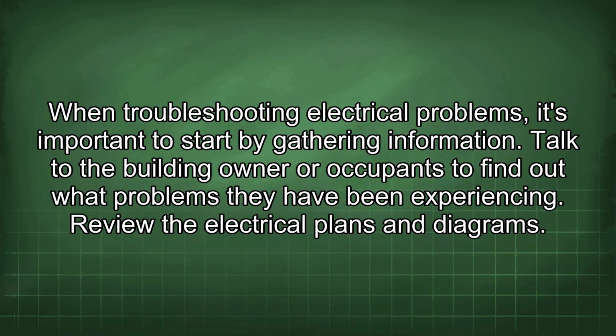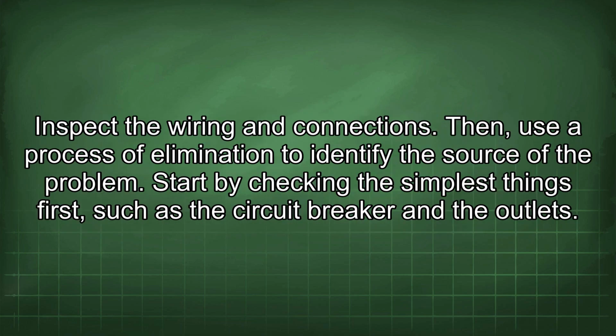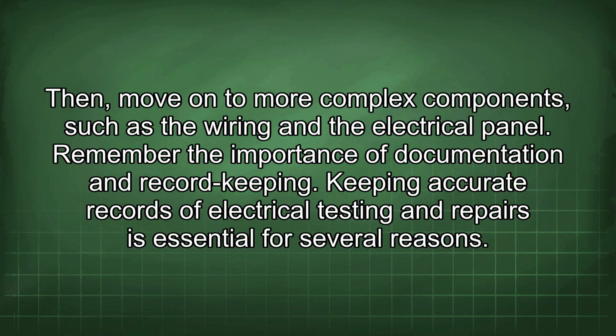When troubleshooting electrical problems, it's important to start by gathering information. Talk to the building owner or occupants to find out what problems they have been experiencing. Review the electrical plans and diagrams. Inspect the wiring and connections. Then, use a process of elimination to identify the source of the problem. Start by checking the simplest things first, such as the circuit breaker and the outlets. Then, move on to more complex components, such as the wiring and the electrical panel.